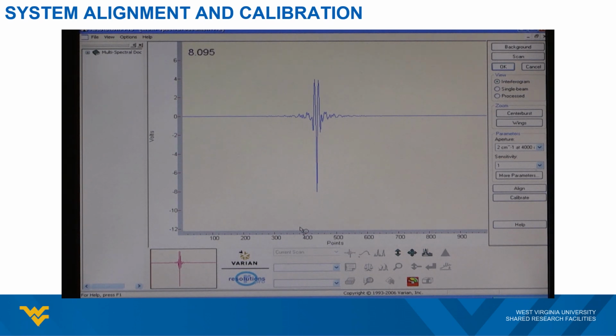Once completed, you will enter the Setup window as shown here. Next, proceed to the Calibration button and click it. This action prompts the system to conduct the calibration, which is a relatively quick process compared to the alignment procedure. The majority of this window is occupied by the center burst display of the FTIR system. Given that we appropriately set all the parameters, after the alignment and the calibration, you should expect an intensity of about 7 to 9 volts, as suggested in the upper left corner of the window.